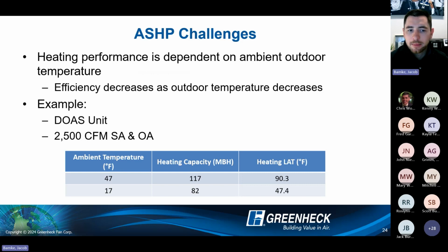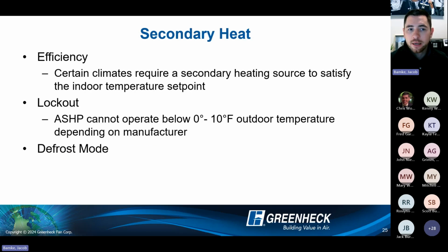As my ambient temperature drops all the way to 17 degrees, which is normally where we're sitting at, that's a mild condition for Wisconsin. But if we're at 17 degrees, we have a heating capacity of 82 MBH. I can only get up to 47.4 degrees. So the benefit of a furnace, you always knew what your temperature rise was if you had a consistent CFM. Didn't matter what the entering temp was. In this case, you can see I go from a 43 degree temperature rise down to a 30 degree temperature rise. So my capacity and efficiency is decreasing enough where it's directly impacting the overall temperature rise that I can get. So that is really where secondary heat will come into play.